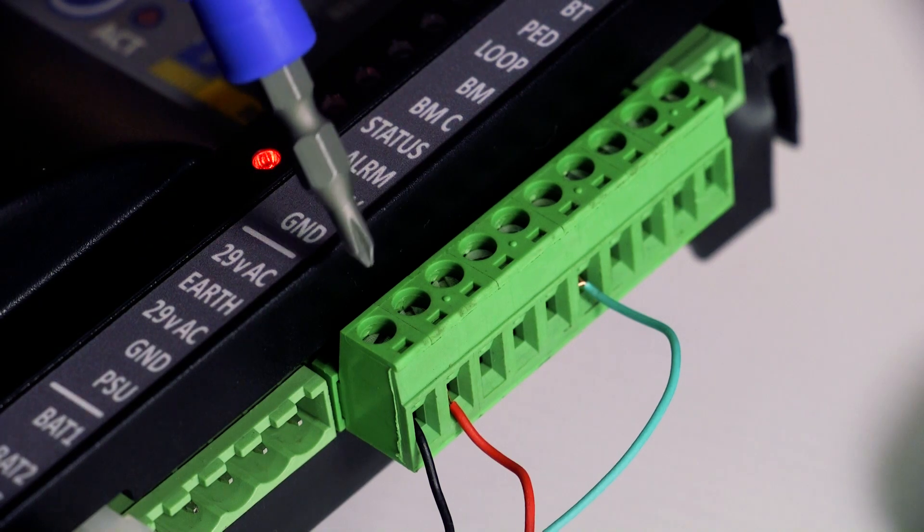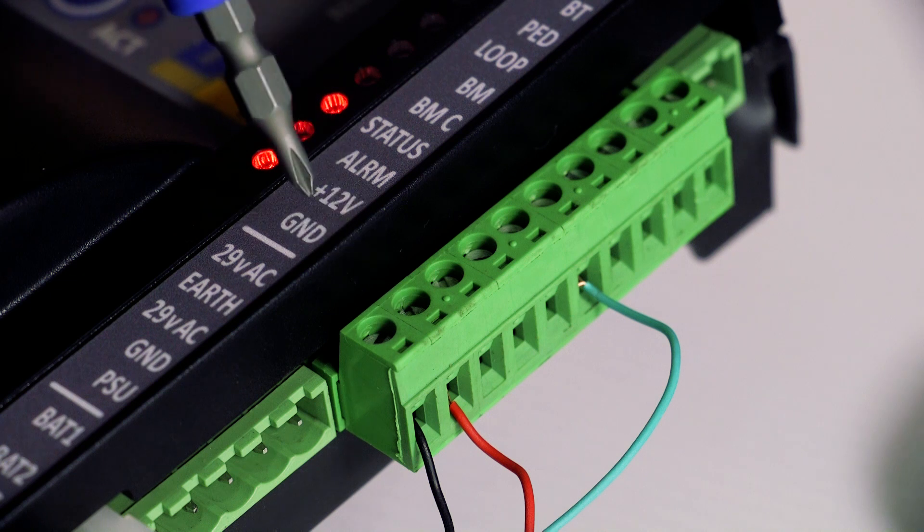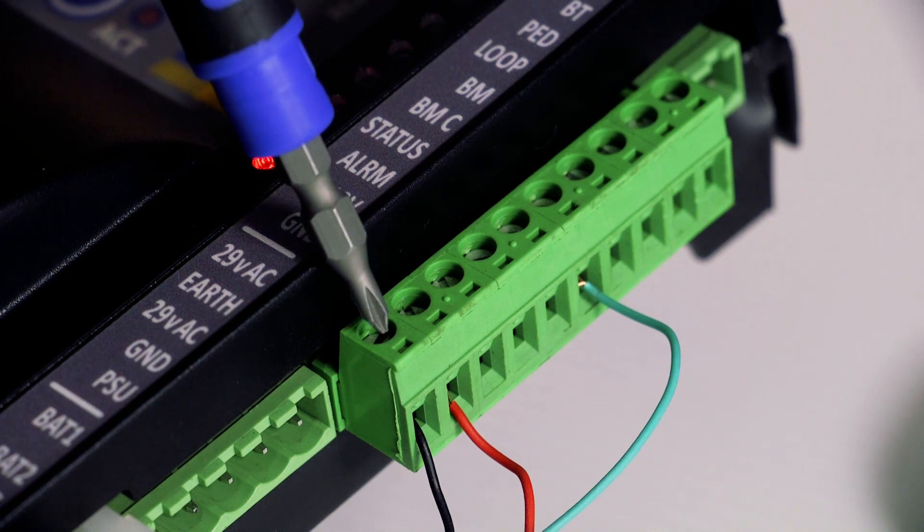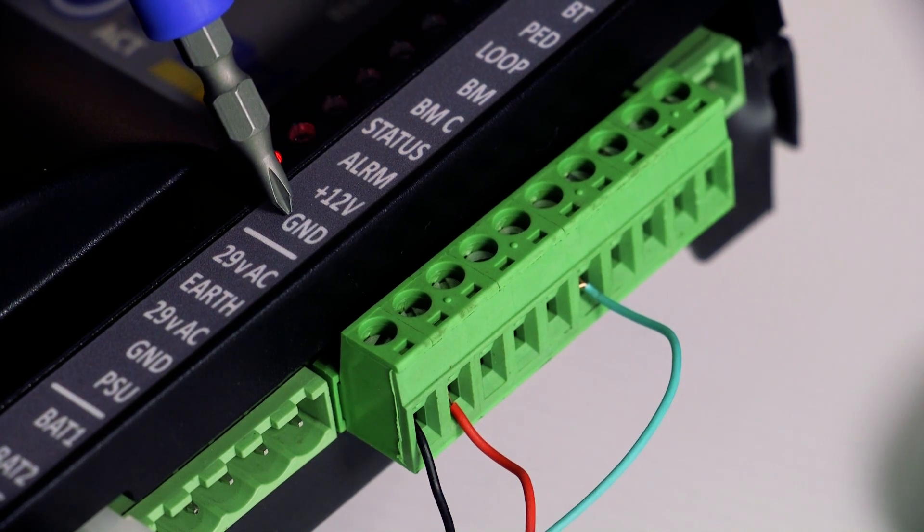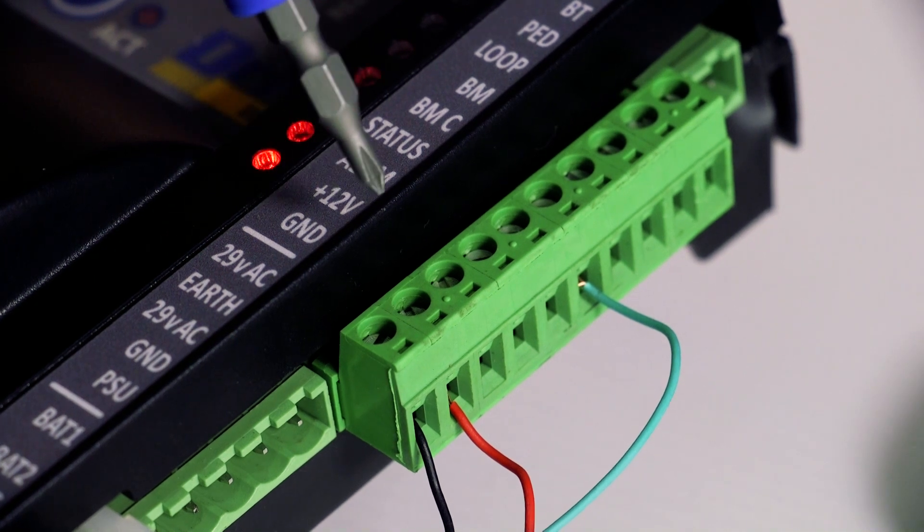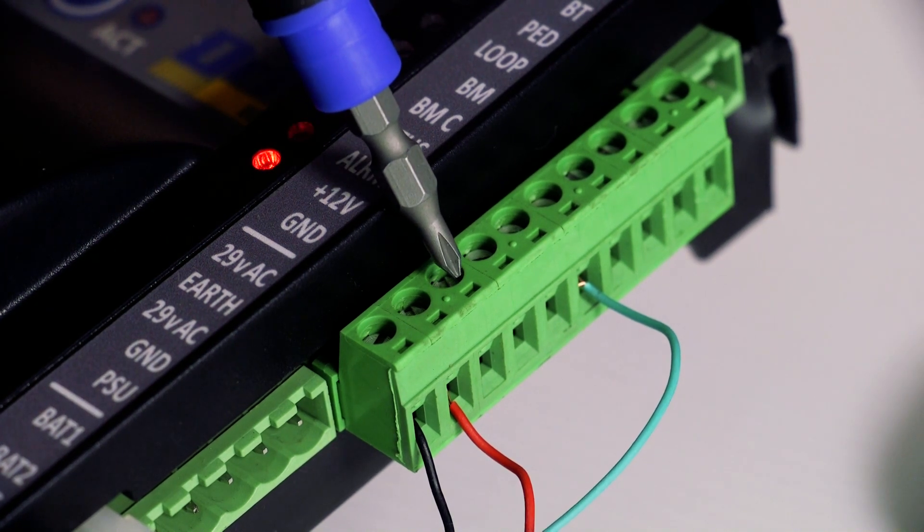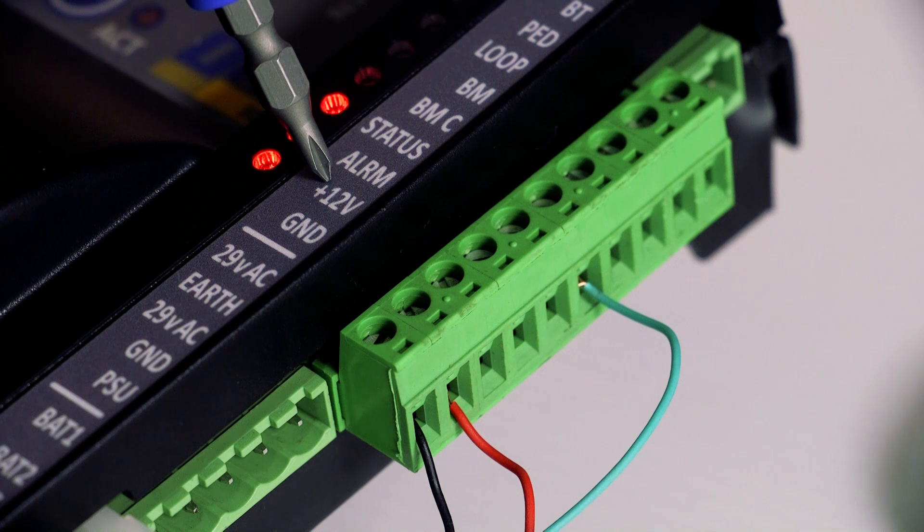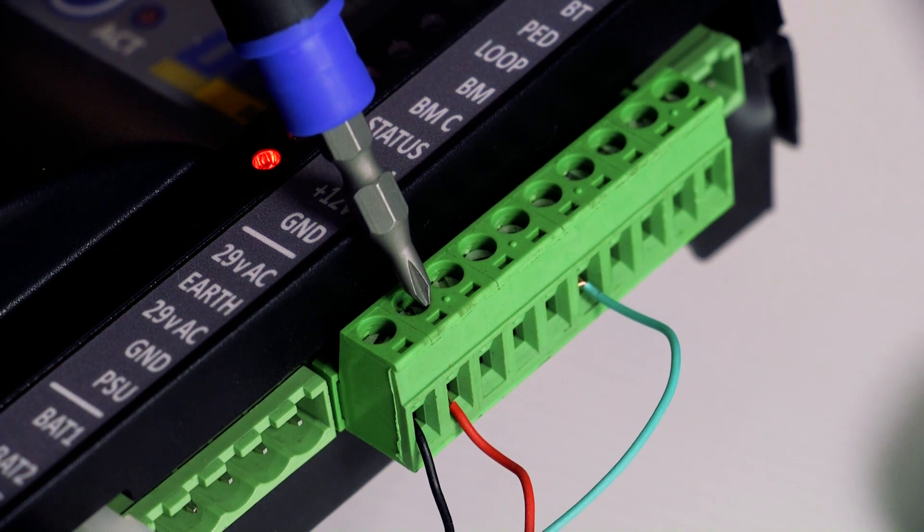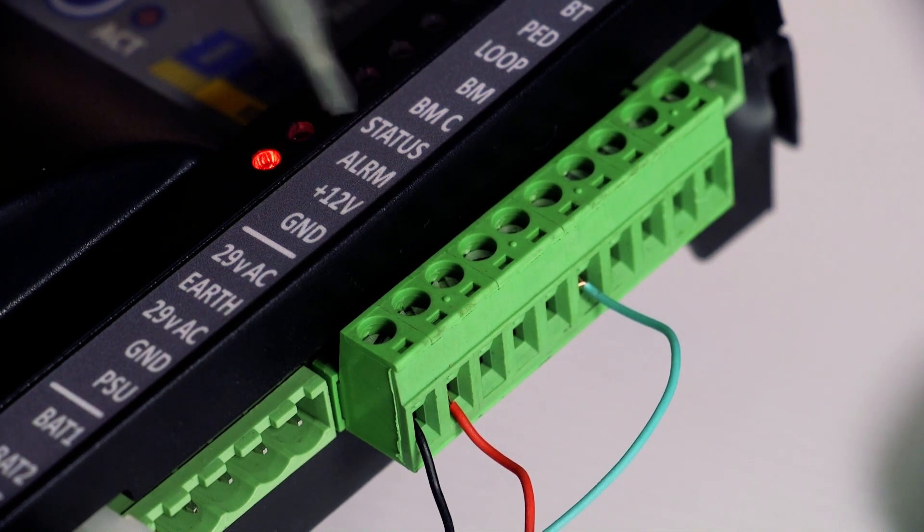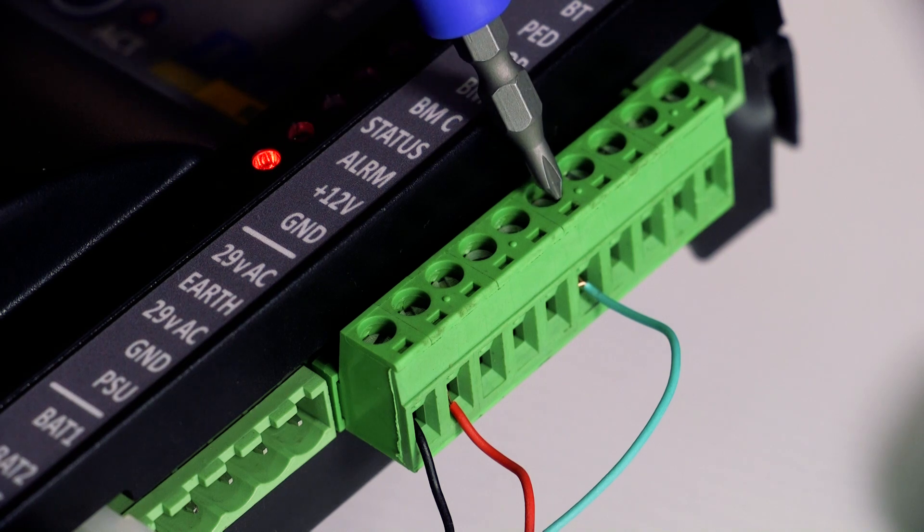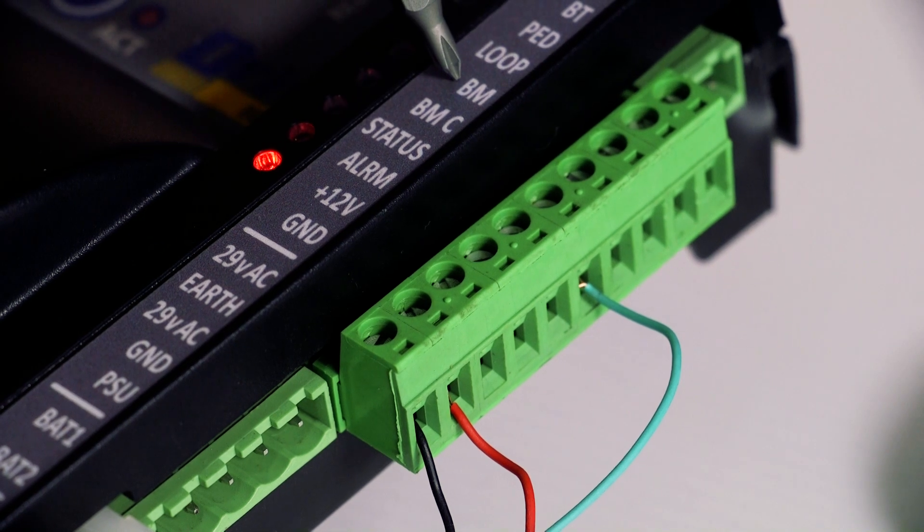connect the prepared negative wire to any of the 0V or GND ground terminals. Connect the prepared positive wire to the positive 12 or positive 24 volt auxiliary terminal. Connect the prepared beam wire to the BM terminal.